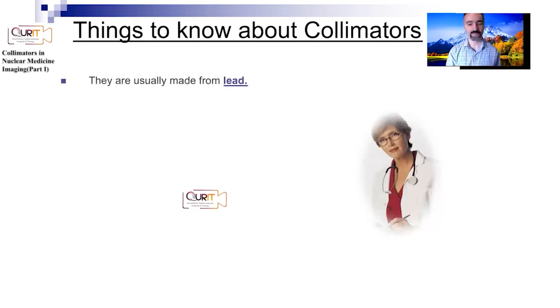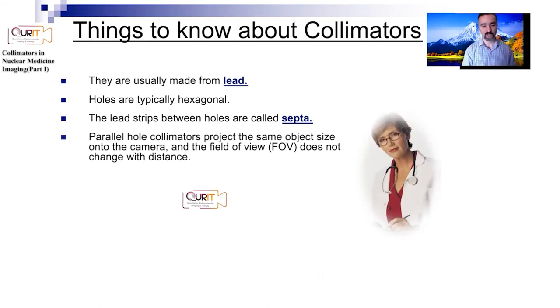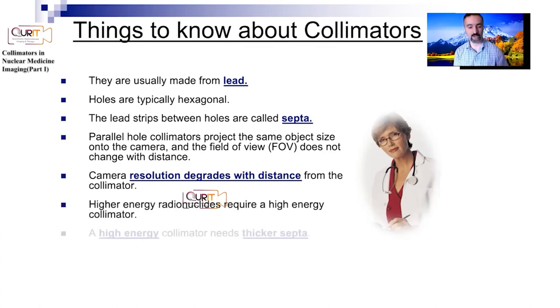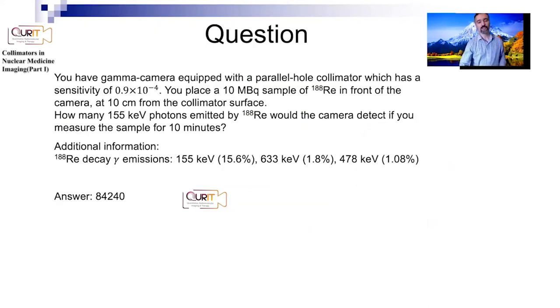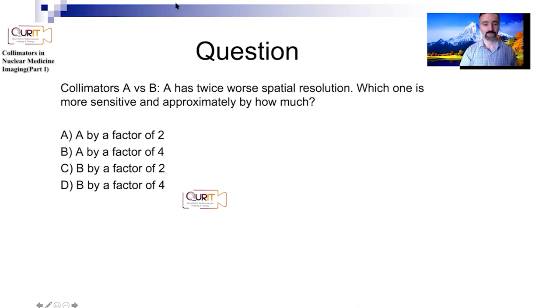Key things to know about collimators: they are usually made from lead; holes are typically hexagonal; the lead strips between holes are called septa; parallel collimators project the same object size regardless of distance from the camera; camera resolution degrades with distance; higher energy isotopes require high energy collimators with thicker septa. There is also a practice problem involving a parallel collimator with a rhenium-188 sample — try to calculate how many counts you'd get in 10 minutes.